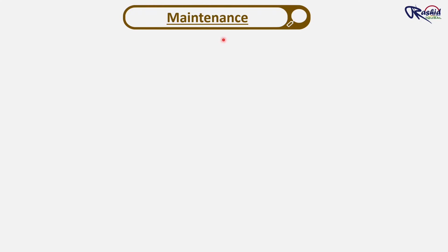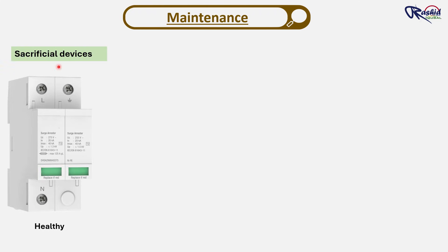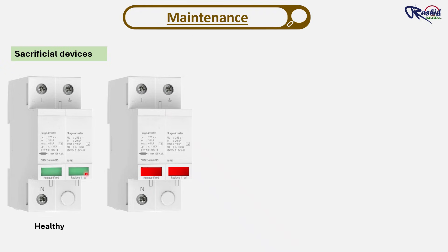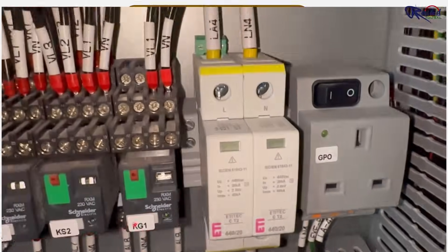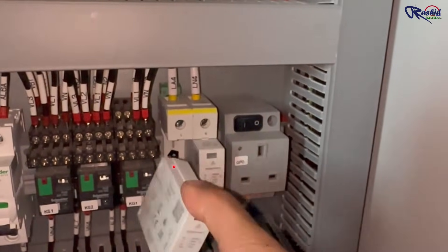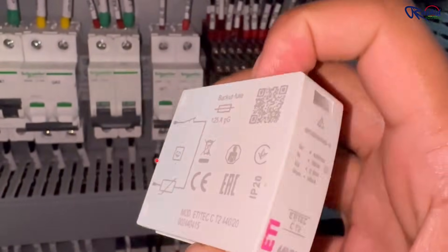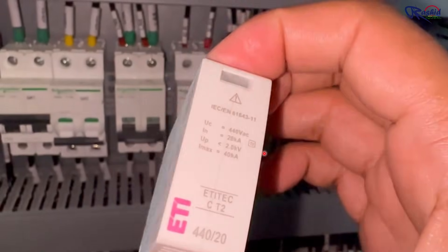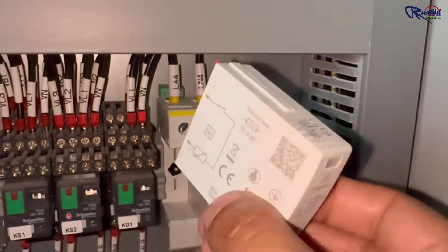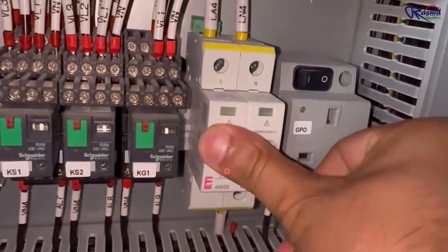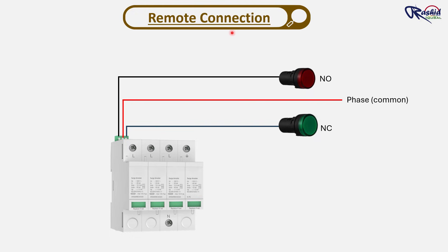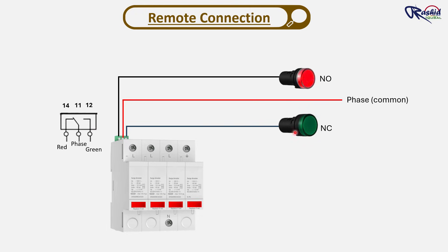Finally, the maintenance of SPDs. SPDs are not maintenance-free — they are sacrificial devices, meaning after protecting from many surges, they can become weak or damaged. That's why manufacturers provide a status indicator: green means the SPD is healthy, and red means it is faulty and the cartridge needs to be replaced. Some advanced SPDs also have remote signaling that connects to a building management system for alarms, so you can identify which SPD is healthy and which is faulty while sitting in a control room.